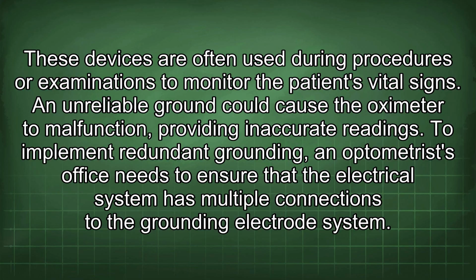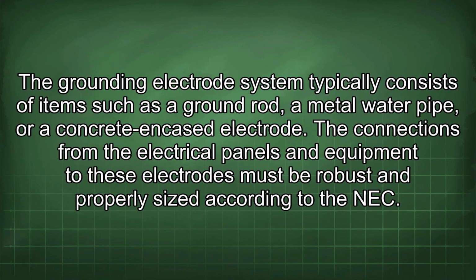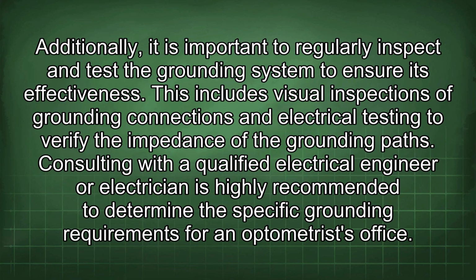To implement redundant grounding, an optometrist's office needs to ensure that the electrical system has multiple connections to the grounding electrode system. The grounding electrode system typically consists of items such as a ground rod, a metal water pipe, or a concrete encased electrode. The connections from the electrical panels and equipment to these electrodes must be robust and properly sized according to the NEC. Additionally, it is important to regularly inspect and test the grounding system to ensure its effectiveness. This includes visual inspections of grounding connections and electrical testing to verify the impedance of the grounding paths.